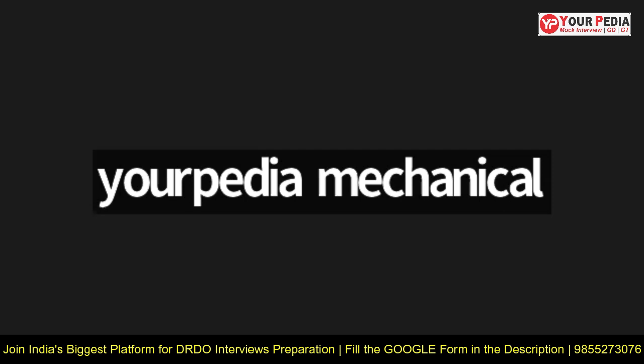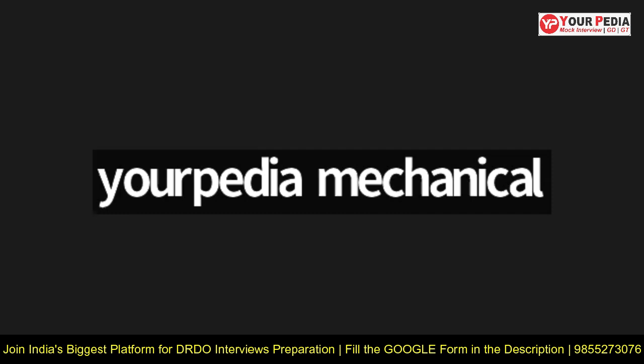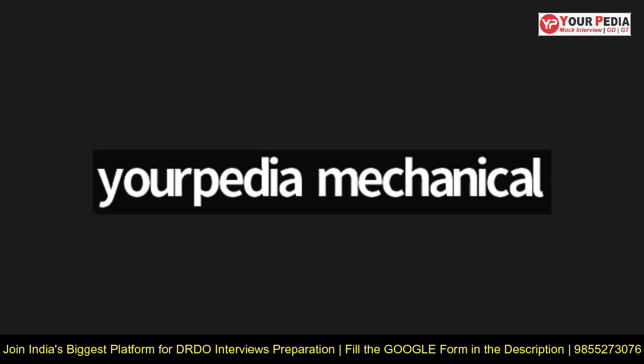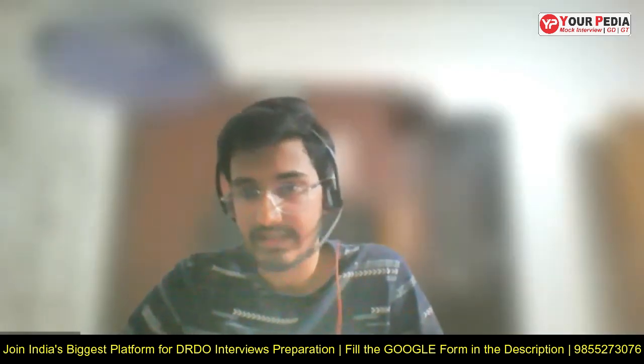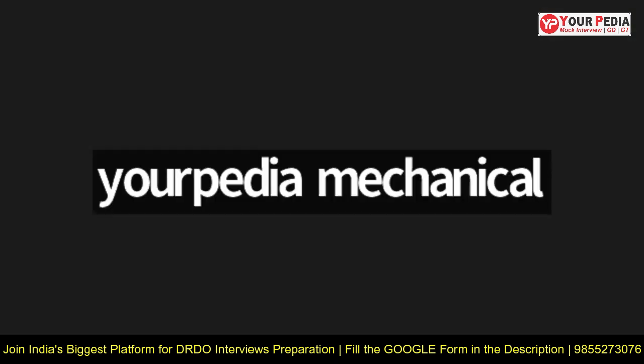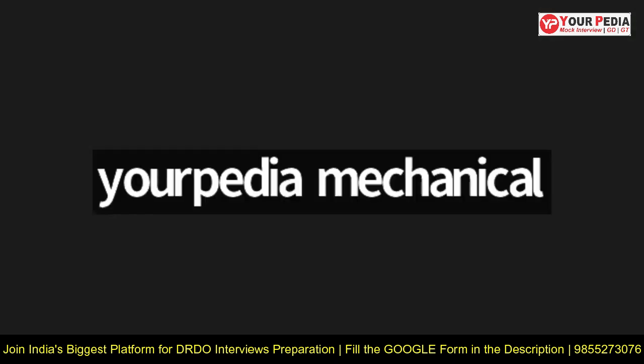Prahlad, what are fins? For what purpose do we use fins? Fins are extended surfaces that are usually used to accelerate the convection heat transfer. Have you seen such kind of fins on some transformer? Yes, sir. How do we provide the fins, vertical fins or horizontal fins? I have seen vertical fins on transformers. Why vertical, why not horizontal? Because vertical fins help in natural convection. Natural convection heat transfer will be more in that case.